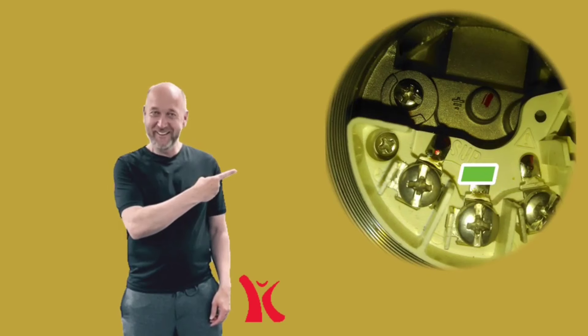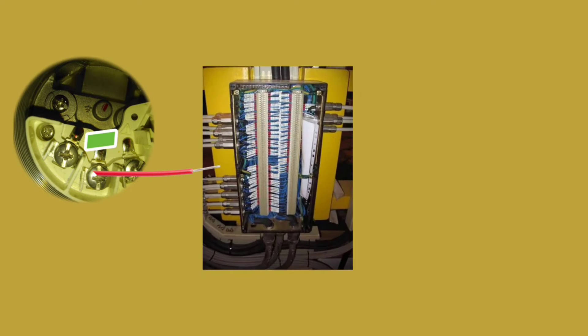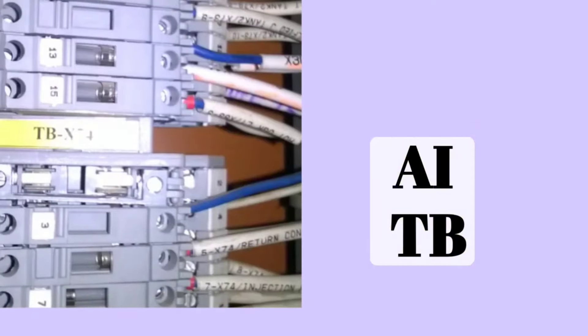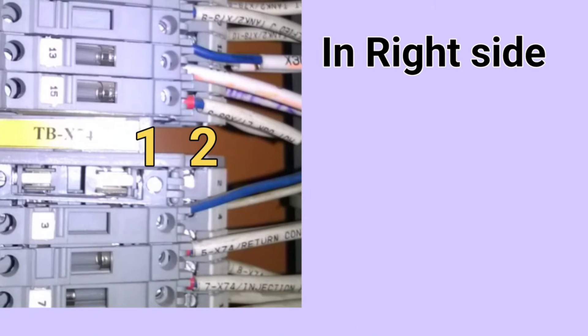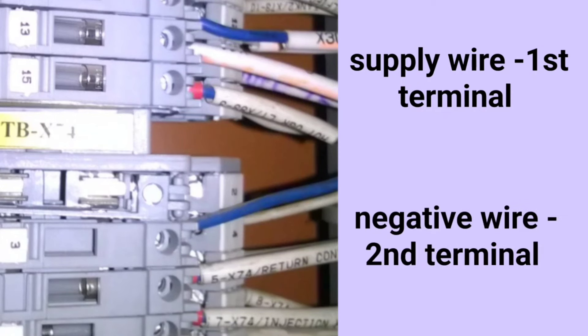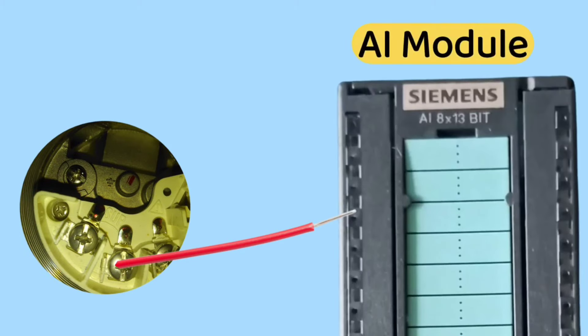Friends, now let us see how the negative terminal of the transmitter is connected to PLC. From the negative terminal of the transmitter, the wire is passed through the same field JB and taken to PLC panel. This wire is also brought to AITB of the PLC. In AITB, for transmitter connections, two terminals are provided. In the first terminal, we connected the supply wire. We will connect this negative wire to the other terminal. After this, we will connect the wire that has come from the negative terminal of the transmitter to the AI card, meaning we will connect it to the AI module.